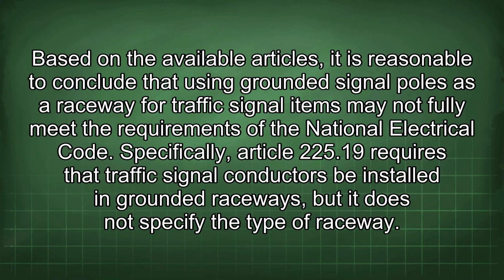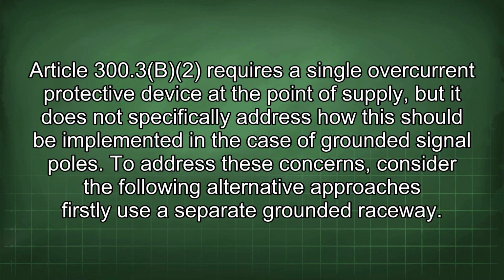Specifically, Article 225.19 requires that traffic signal conductors be installed in grounded raceways, but it does not specify the type of raceway. Article 300.3b2 requires a single overcurrent protective device at the point of supply, but it does not specifically address how this should be implemented in the case of grounded signal poles. To address these concerns, consider the following alternative approaches.